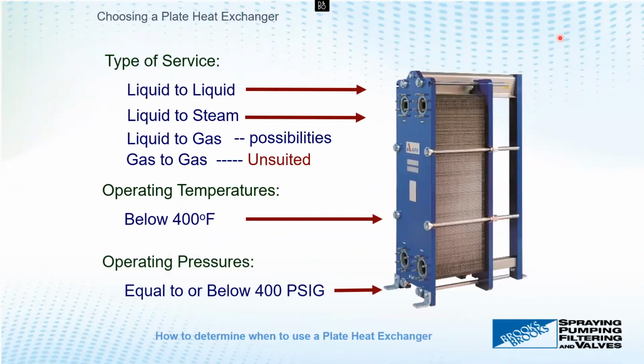In the decision tree, if you can use a plate and frame heat exchanger, we talked about pressures and temperatures, we talked about fluids, but really what plate and frames love is liquid to liquid service: water to glycol, diluted bitumen to glycol, water to water. Steam in some cases is absolutely fine, as long as there's not too much steam by percentage. Liquid to steam is very common. No problems. Once we start getting into liquid to gas, plate and frame heat exchangers don't like gas very much. It is possible, but we have to look at that on a specific case-by-case basis.